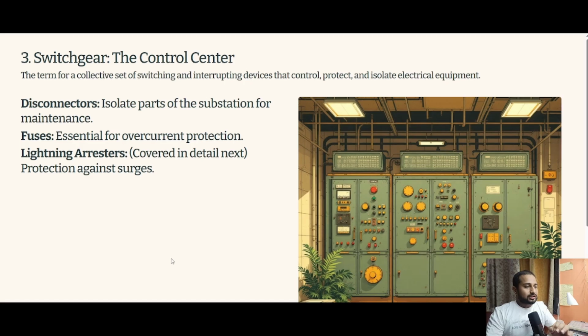The switchgear term is a collective set of switching and interrupting devices that control, protect, and isolate the electrical equipment. They include disconnectors that isolate the parts of the substation for maintenance, and it also includes fuses. Those are essential for overcurrent protection.